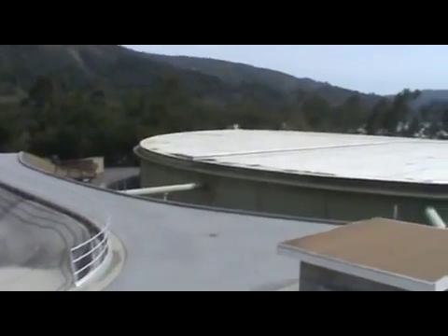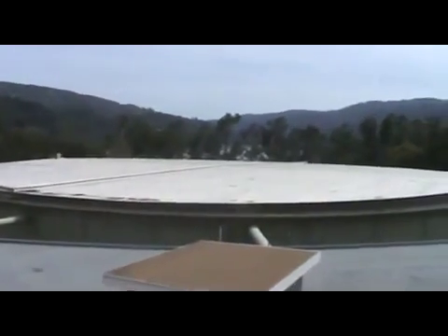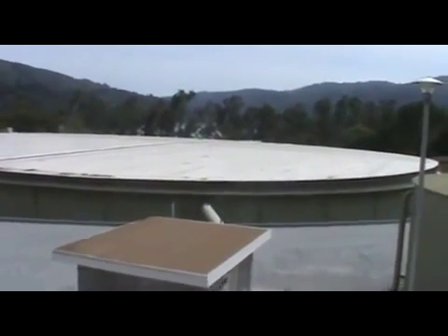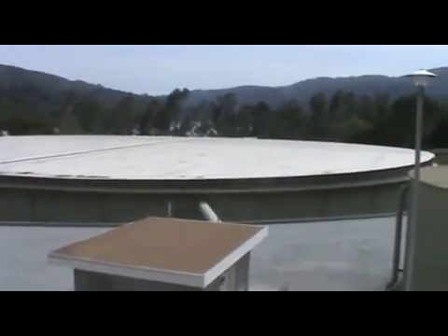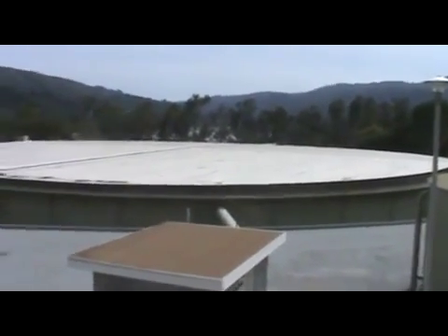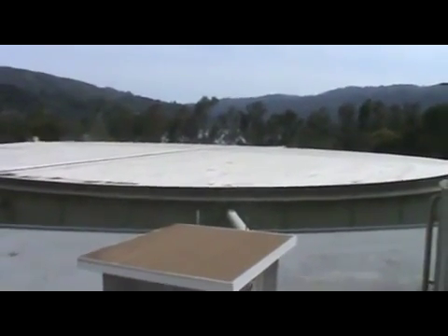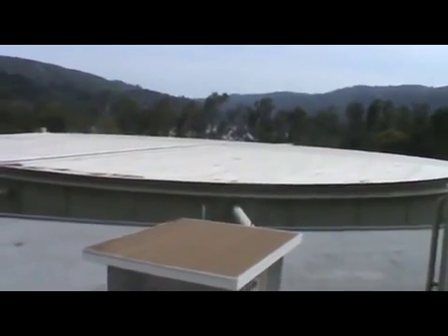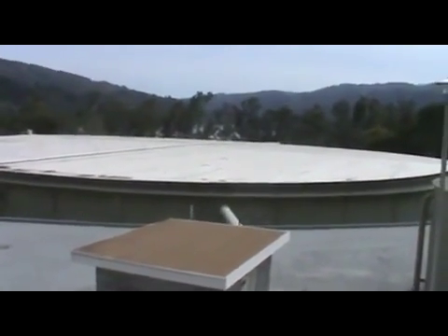And then the water is sent to a holding tank, which is called a clear well. In this case, that is the clear well. What the clear well does is allow for contact time before going out into the system, so that anything that might still be in the water has time for that chlorine to react with it and kill it. This plant here has two clear wells. There's that one right there, and there's another one there on the other side of that wall.